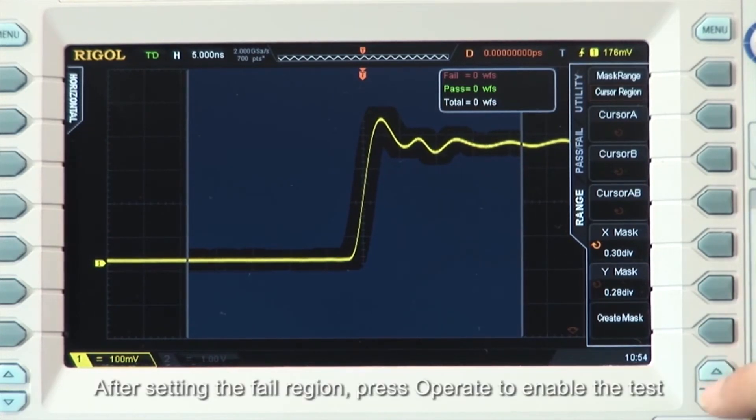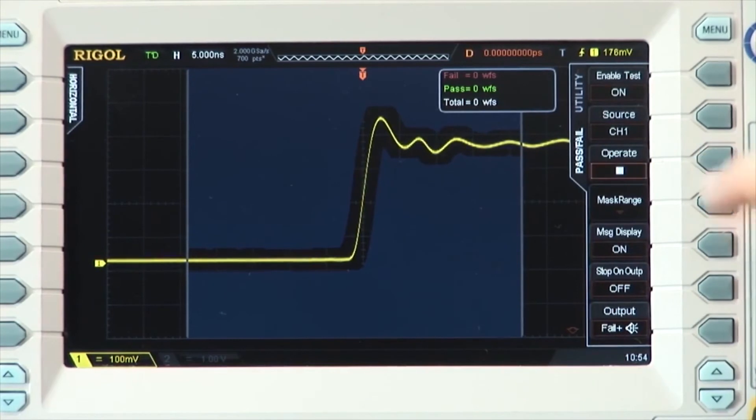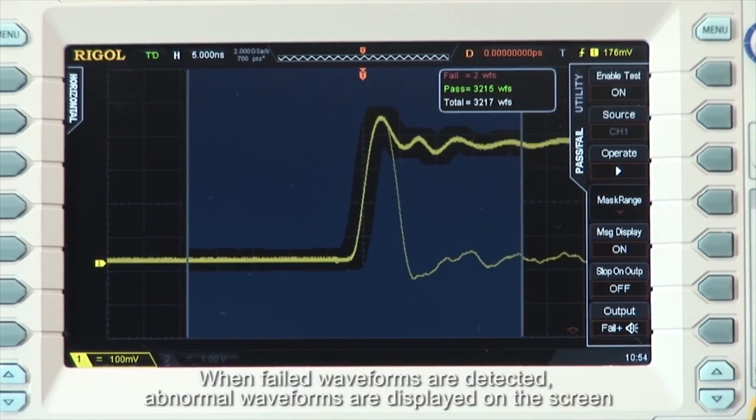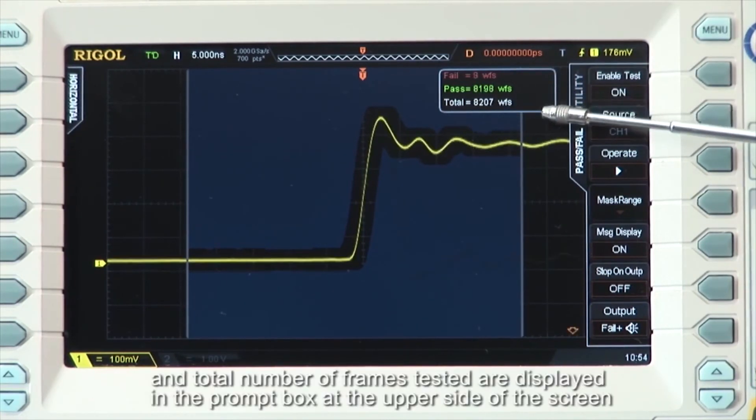After setting the fail region, press Operate to enable the test. When failed waveforms are detected, abnormal waveforms are displayed on the screen, and the current number of failed frames, number of passed frames, and total number of frames tested are displayed in the prompt box at the upper right side of the screen.